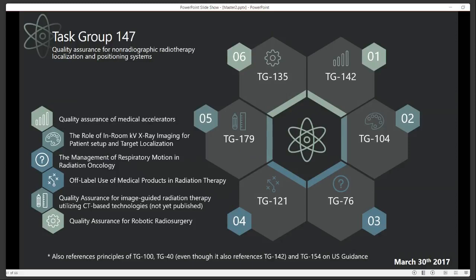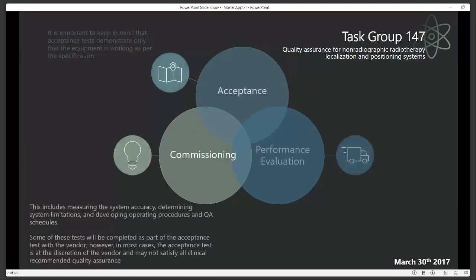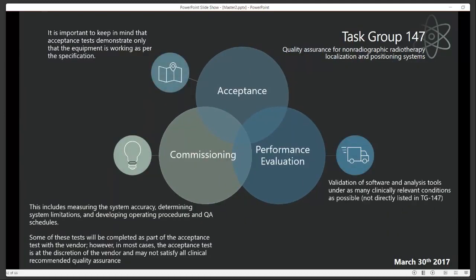It references TG76, TG121 directly in the text. It also references principles in TG100 and TG40. Even though TG142 does kind of supersede TG40, it does mention TG40 by name, and also has a couple references to TG154. So it's a good all-around place to go to look and see what you need to do. It does cover acceptance and commissioning directly. It does acknowledge that there is an overlap between acceptance and commissioning, but it does make a distinction between the two.